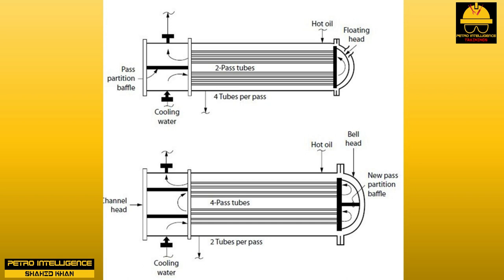Let me explain. Let's say your sea water pumps develop a 40 psig discharge pressure and the sea water return line operates at 5 psig. The pressure drop of sea water flowing through the exchanger is 35 psig, regardless of the exchanger geometry. If the water flow is restricted by increasing the number of tube side passes, then both total water flow and the tube side velocity will decrease. When the plant changed from two-pass to four-pass, the water flow decreased from 1 million pounds per hour to 350,000 pounds per hour.